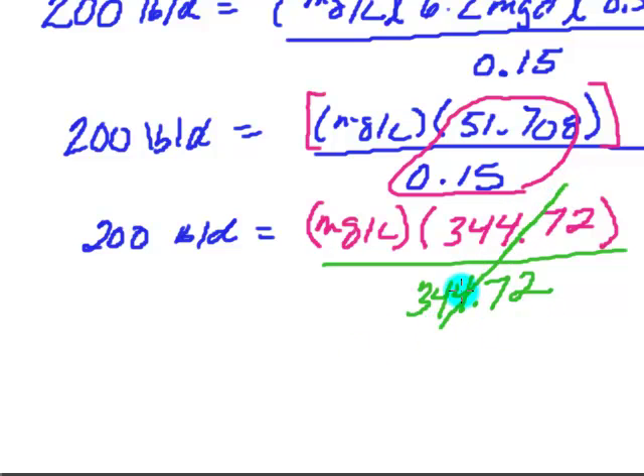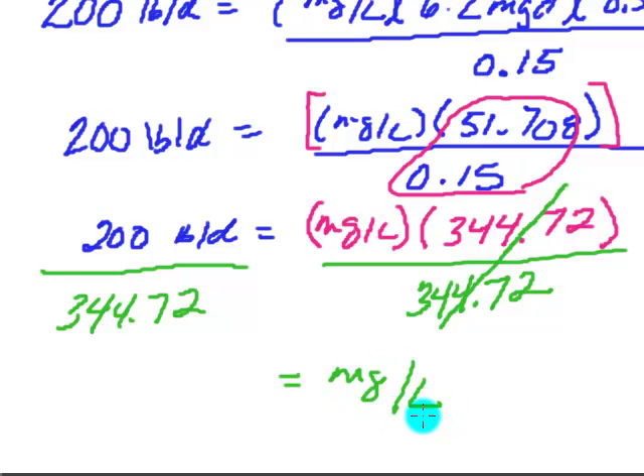But since I did it to one side, I have to go back and do it to the other side. So here is my 344.72 dividing. And what I'm going to end up with is my answer in milligrams per liter. So this is 200 divided by 344.72, and it looks like my dose at the treatment plant is about 0.58 or 0.6 milligrams per liter of chlorine.